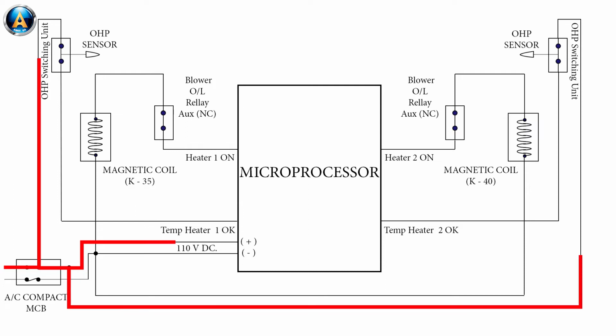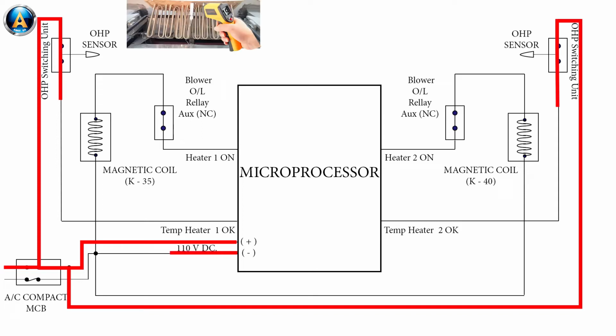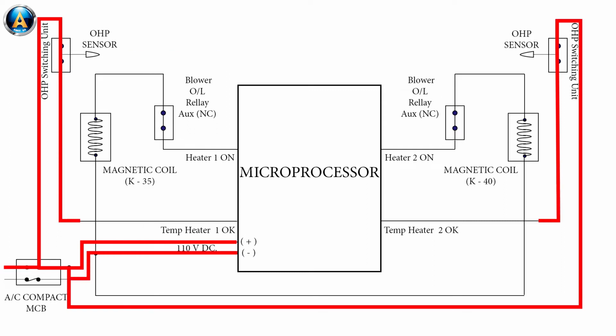110 volt DC power is available to the incoming of the OHP device if the AC compact MCB stays on, and that power continues through the OHP if the temperature near the heater coil stays below 65 degrees centigrade. And finally, that power comes to the terminal of temperature heater OK of the microprocessor, like this.